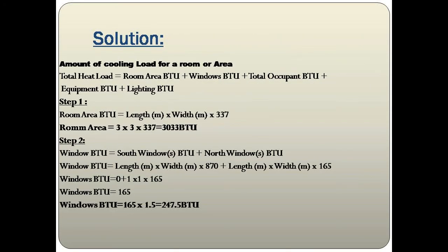The total heat load formula is: Room Area BTU + Windows BTU + Occupants BTU + Equipment BTU + Lighting BTU. Step 1 — Room Area BTU = length × width × 337 = 3 × 3 × 337 = 3,033 BTU.